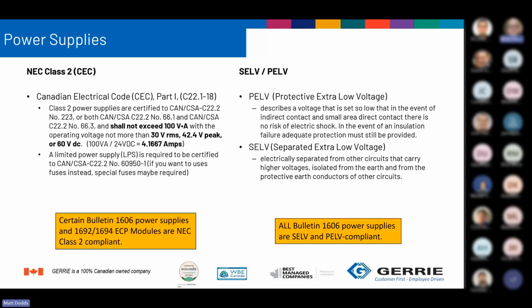You can also use electronic circuit protection modules that are NEC National Code Class 2 compliant. And then in Europe, we have SELV and PELV, so separated extra low voltage and protective extra low voltage. So again, if you're shipping machines to Europe, all 1606 power supplies are SELV and PELV compliant, and certain models are NEC Class 2 compliant, typically limited to a maximum of 100 volt-amps, or approximately 4.2 amps.